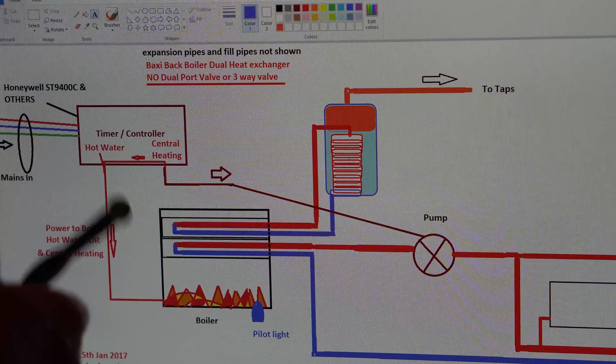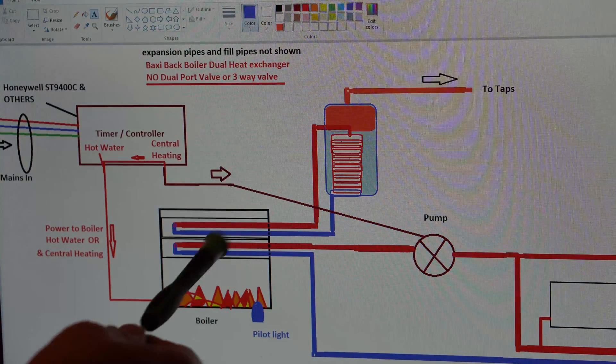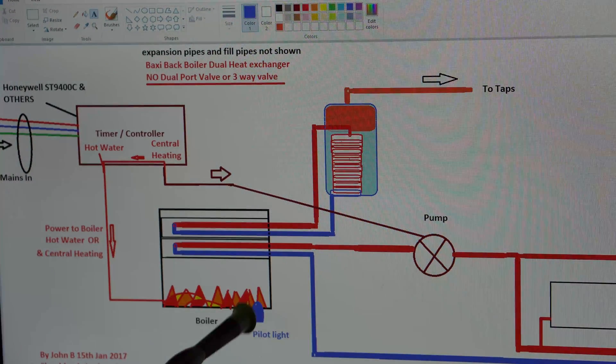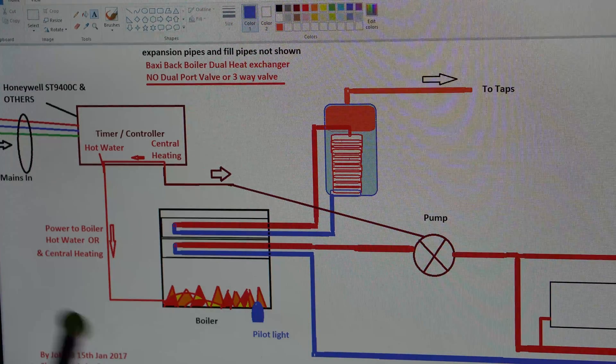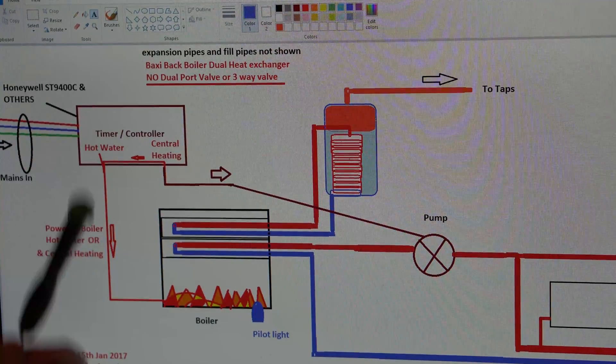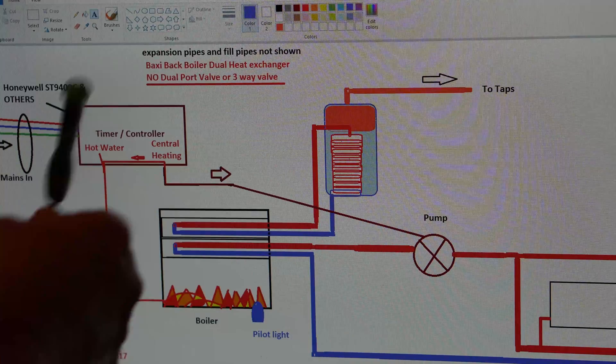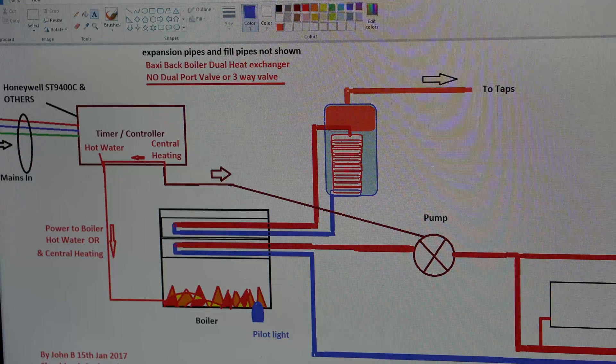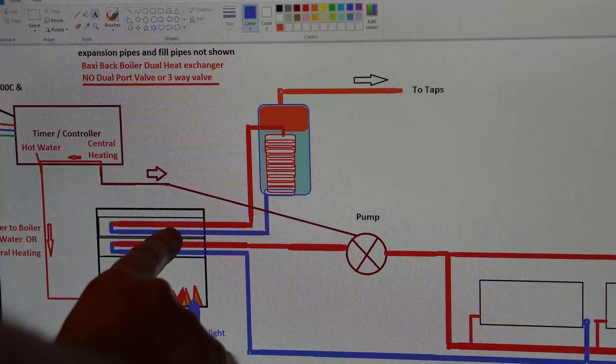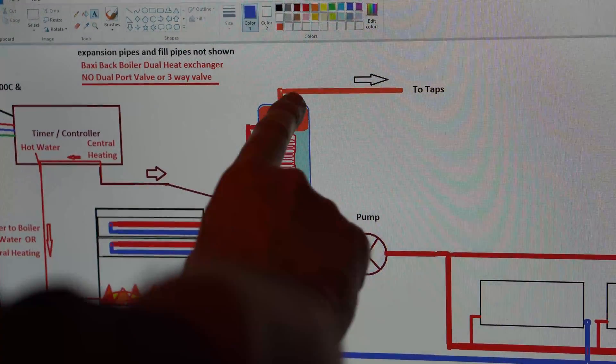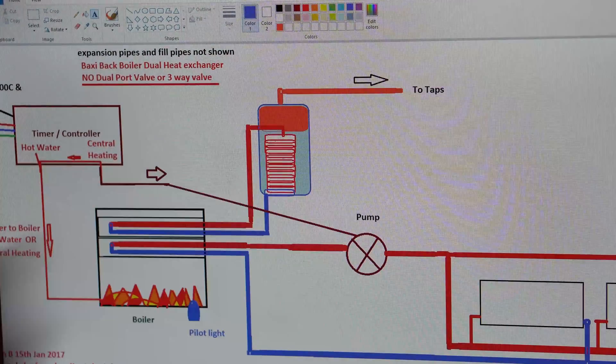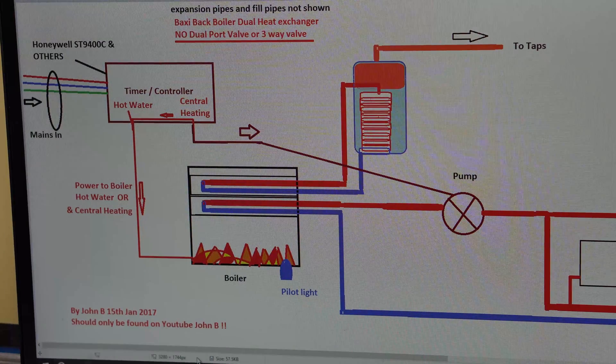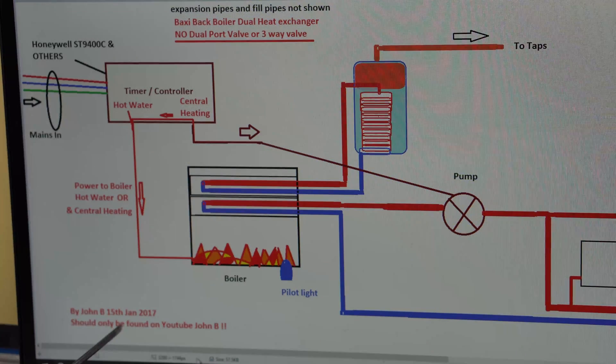And the problem is this. Sometimes you'd have hot water. Sometimes the heating worked. If you turn the heating on by itself, you'd get nothing. There's power to turn on the pump, but no power to bring on the second relay to light up the boiler. So depending on what you requested, you'd get different faults. The hot water heat exchanger heats up the water, heats up the coil in the tank, and you've got the hot water out to the taps. The cold fill would be at the bottom of the tank. Hopefully you're not getting too many weird effects for this camera viewing this monitor.